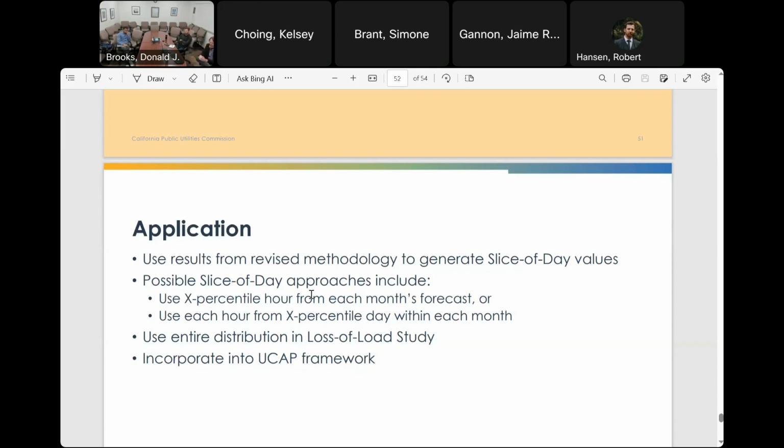So question for Robert. On this revised methodology, I'm just wondering, have you looked at what this would mean during some of the extreme weather events that we've had over the last few years? Like the August 2020 events or the September 2022 events, what type of a derate would we be seeing in some of the natural gas plants during those events? And then also comparing what this model would suggest those derates would be on those days to actual bid and output data from some plants during that time.